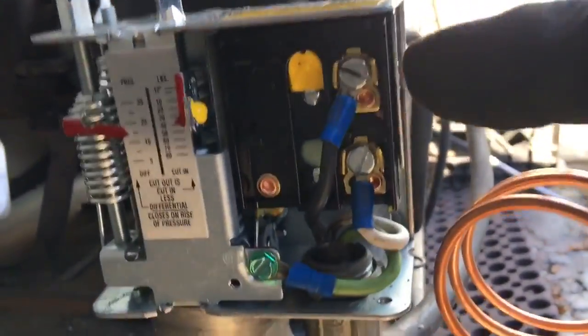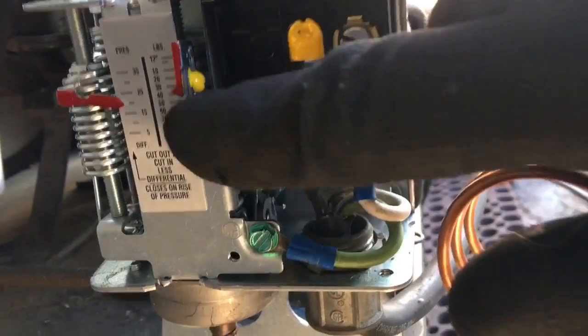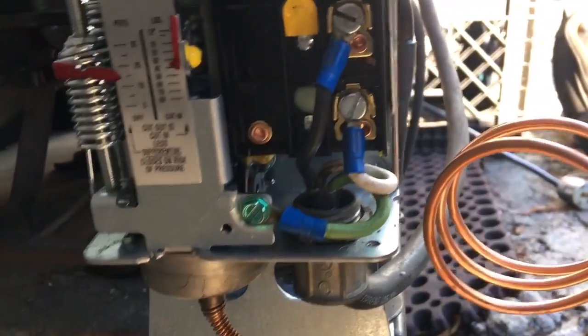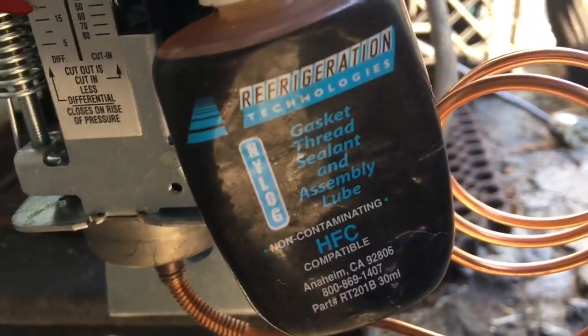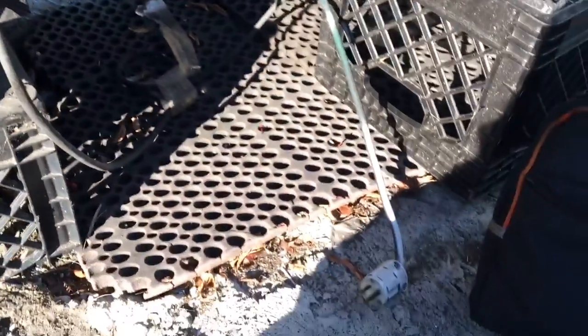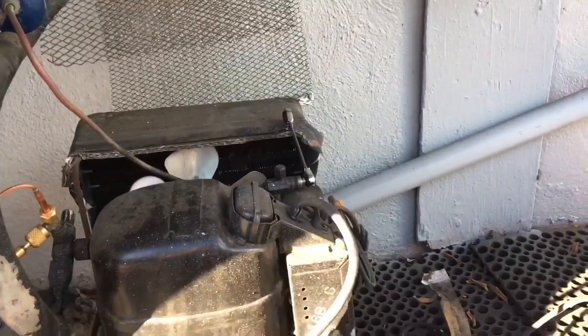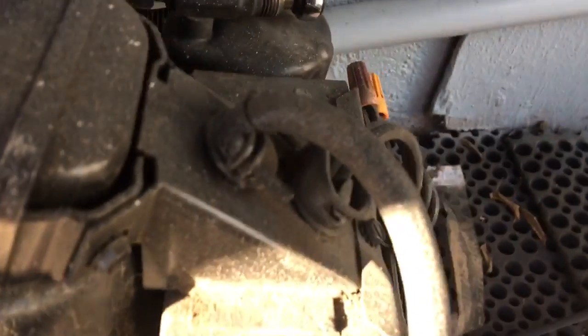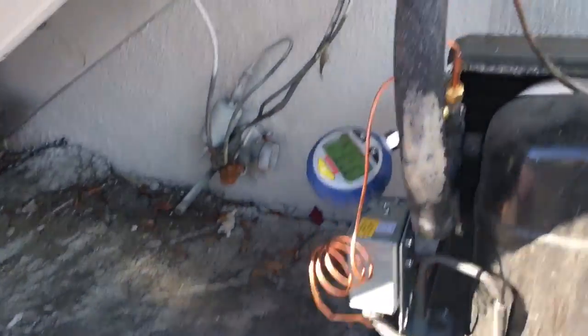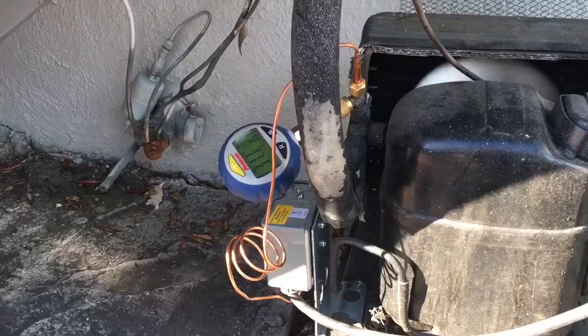So there's the new switch. It's just basically line, load, and your ground. We're going to set the pressures — don't ever go by the numbers on these switches, they're never close. Got some Nylog we're going to put up here and make a connection. Switches are all installed, got my gauge on there. I'm going to plug it in now. What I do is go ahead and drive the receiver King's valve closed, get her pumped out, and then what I want to set is my cut-in first.